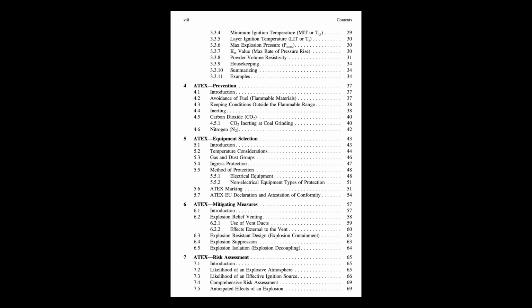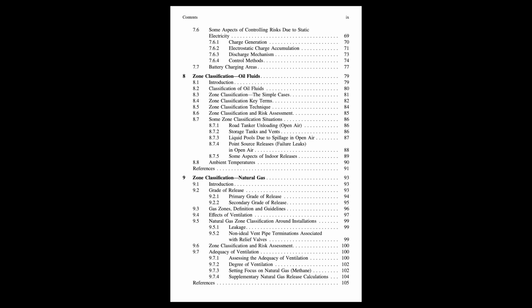In open, well-ventilated areas, generally yes. Continuous release typically leads to zone 0 or 20. Primary release leads to zone 1 or 21. Secondary release leads to zone 2 or 22. But you said well-ventilated areas. Does ventilation affect the grade of release?